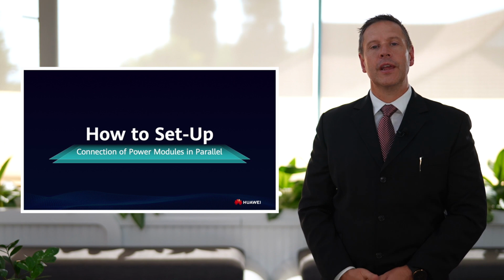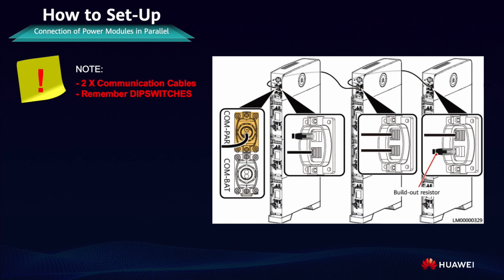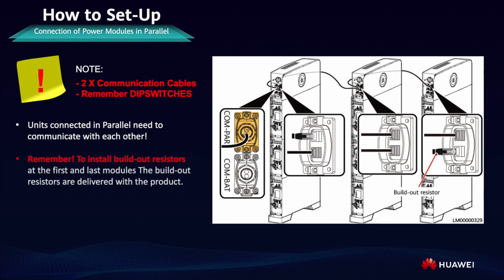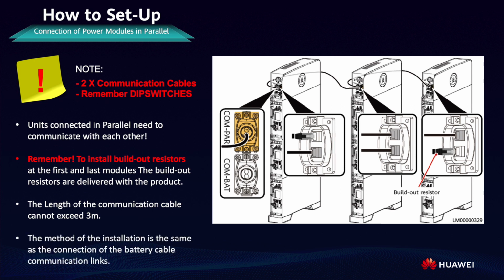Connection of units connected in parallel. It's important to note that there are two communication cables, and remember to change the dip switches. Units connected in parallel need to communicate with each other. Remember to install build-out resistors at the first and last modules. The build-out resistors are delivered with the product. The length of the communication cable cannot exceed 3 meters. The method of installation is the same as the connection of the battery cable communication links.